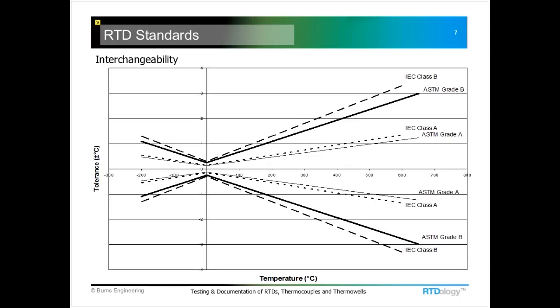You can also look at this graphically, and you can see pretty easily the difference here between the two standards. The IEC has a little wider tolerance band than the ASTM does. And down here at 0 degrees C, the manufacturers adjust the sensors or the actual sensing element as close as they can get it to 100 ohms. And these lines are the tolerance bands because unfortunately we can't do it to exactly 100 ohms. There's always a little tolerance band associated with that.